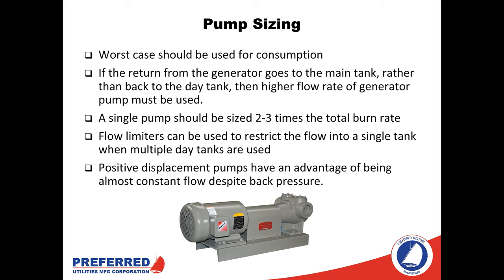We don't necessarily want to supply 10 times the flow rate into one tank, which would require upsizing all valves as well as any return pumps associated with that day tank. One advantage of using positive displacement pumps — which is the standard for our transfer skids and recommended by international mechanical code — is that they have almost constant flow that doesn't depend on back pressure. So in the design phase, even if we don't know exactly how many valves or elbows are on the discharge side, we know our flow rate will be fairly constant.